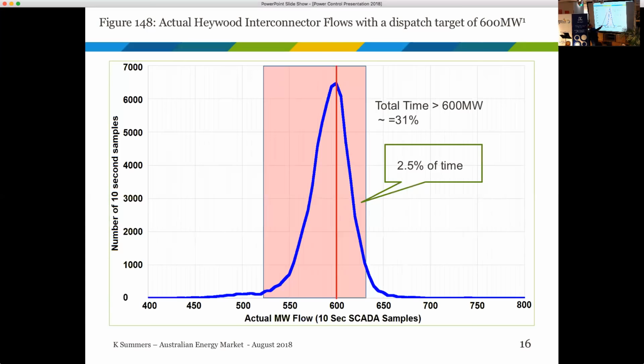As you can see, they're actually trying to maintain 580, not 600. In this box, it's 2.5% of the time they're well over the secure limit, and a total of 31% of the time they're actually outside of the limit. This is not secure operation of the power system. So if you think about critical clearing time, trying to save the power system from overloads and so on, this is what the actual control systems are doing.